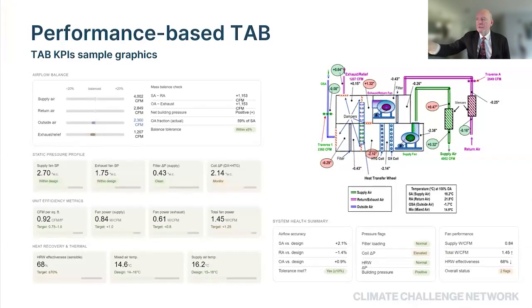The pink highlighted numbers are excessive static pressures between the return air fan at the top and the supply air fan intake at the bottom. That plus to minus number, that's outrageous and indicates quite likely that the recirculation damper is not functioning. The intake is the intake in the bottom left-hand corner there. That intake compared to upstream suggests that there are restrictions on the air intake. On the right-hand side, the input static to that silencer is beyond what it should be. These things are all correctable, and they have to be corrected.